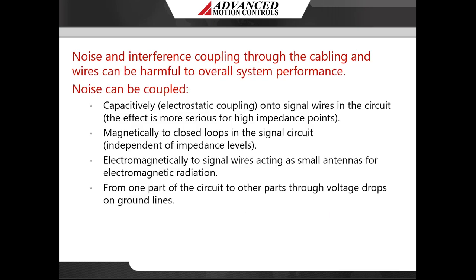EMI, either radiated or conducted, can disrupt the proper operation of electronic equipment. If sets of wires run close to each other, signals between the wires tend to couple one another, consequently introducing noise, also referred to as crosstalk. Crosstalk may have negative effects if the coupling occurs between power and signal cables. EMI can potentially affect sensitive components in the system, such as sensors, analog signals, as well as communication and feedback data.